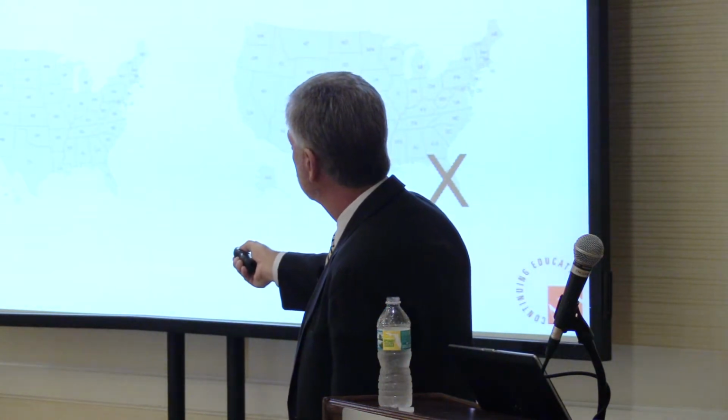Florida did not allow VAV control in any spaces in the hospital. And what many of our hospital clients were under the assumption was that changing the air changes per hour in critical spaces qualified as a VAV conversion. That's really not the true definition, as we're going to try to lay out today. And certainly there's a tremendous amount of energy that can be saved if this can be done, and you'll see that here in a moment.